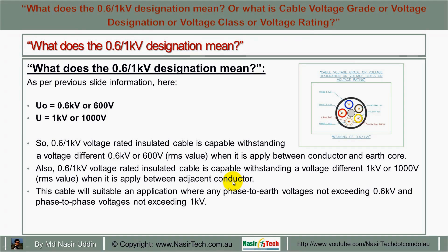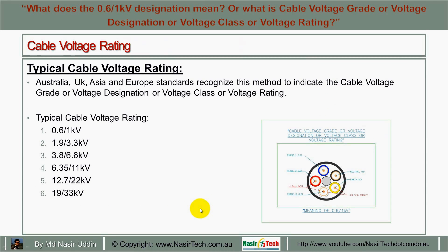This cable will be suitable for applications where any phase-to-earth voltage does not exceed 0.6 kV and phase-to-phase voltage does not exceed 1 kV. This standard is recognized in Australia, UK, Asia, and Europe.